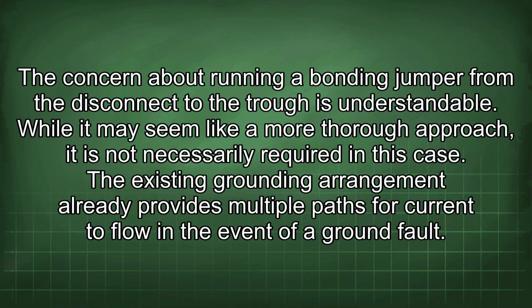The concern about running a bonding jumper from the disconnect to the trough is understandable. While it may seem like a more thorough approach, it is not necessarily required in this case. The existing grounding arrangement already provides multiple paths for current to flow in the event of a ground fault.